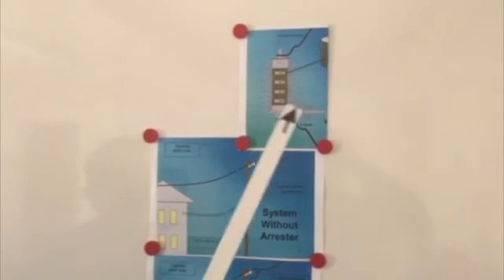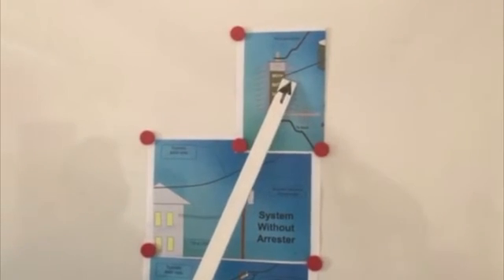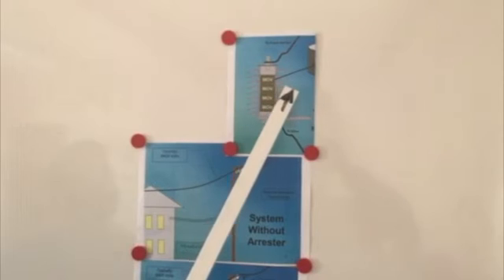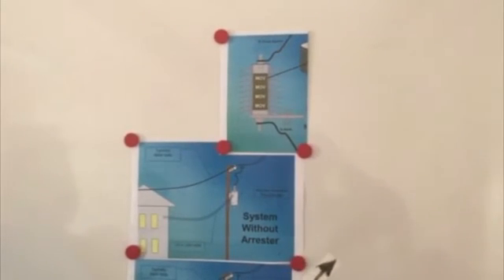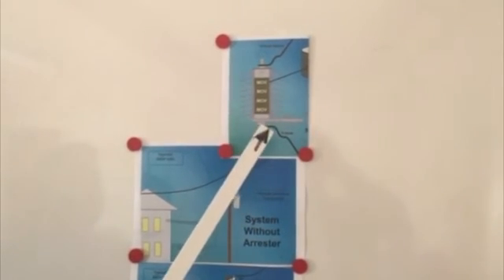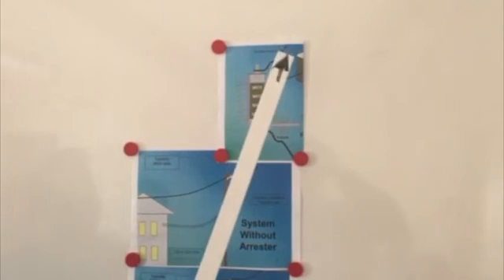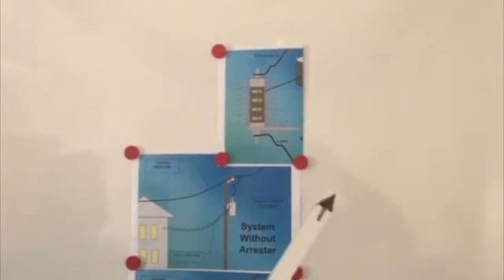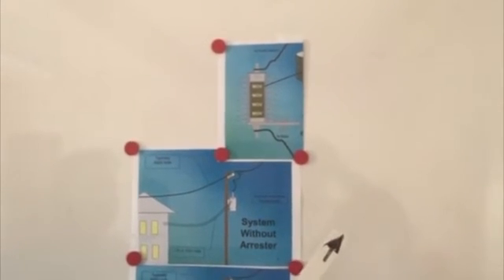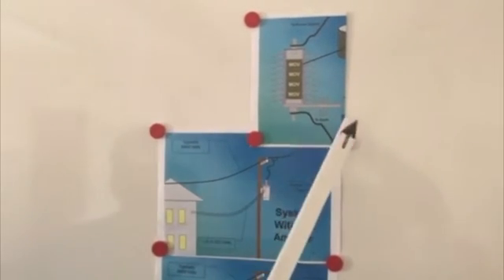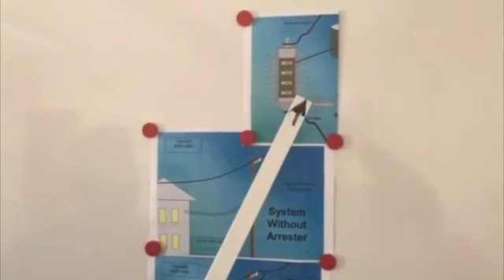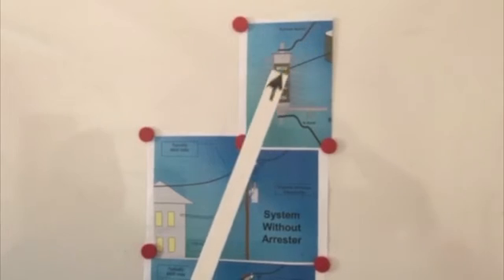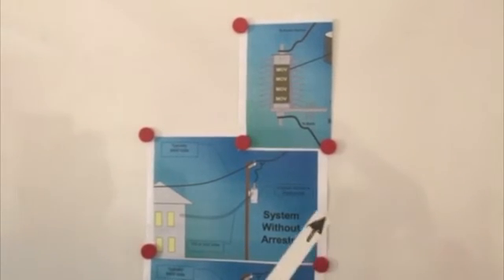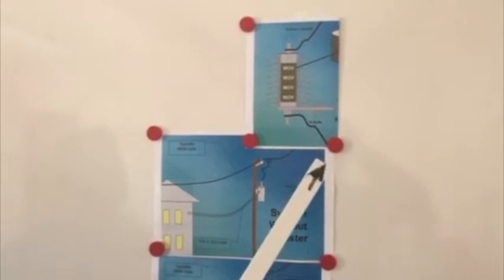Surge arrestors work by having multiple layers of MOVs. These are metal oxide varistors. In normal conditions, the MOV acts as an insulator. Thus, the voltage will flow through its normal path through a transformer or any other equipment. If a large voltage spike occurs, the MOV acts as a conductor. This thus diverts the large voltage to earth, and hence you would protect any sensitive equipment.